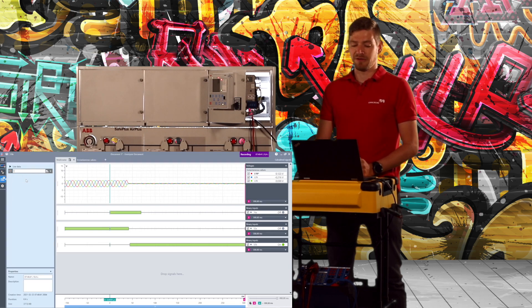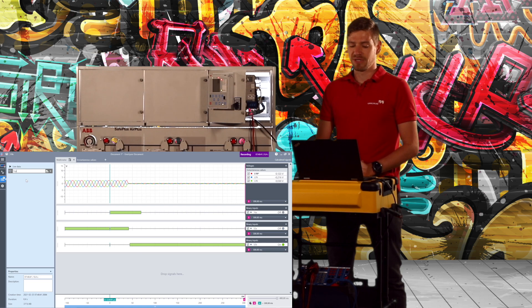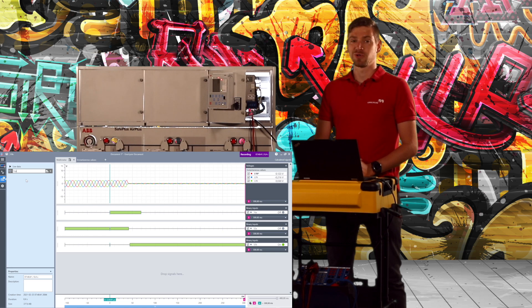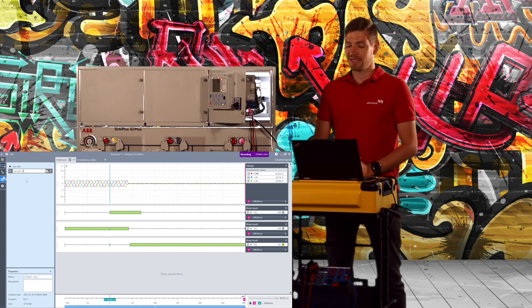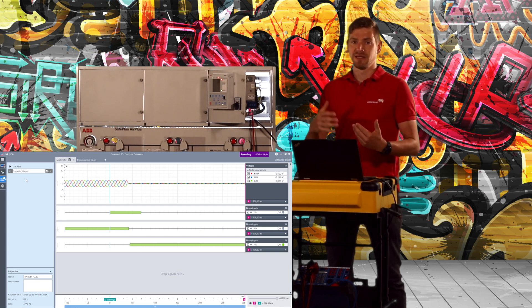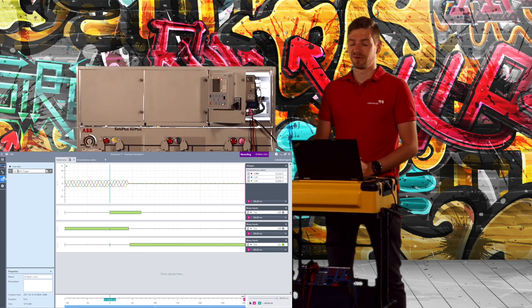I now have a new measurement I can analyze, and what I see here is the toggling of the auxiliary contacts and the voltage of the sensors is going down.